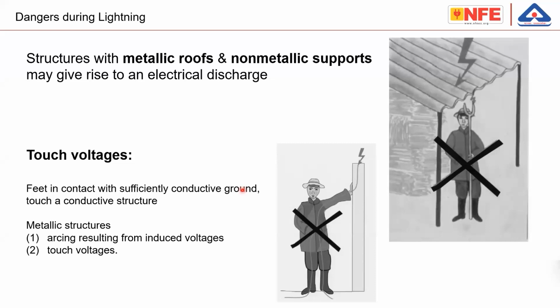Whereas if you are standing outside any kind of building and touching the metallic part, this problem exists. So touch voltage exists outside the building. I repeat: if you are standing inside a building which has steel reinforcement and protective equipotential bonding as per IS 732 or National Electrical Code, then inside the building this problem doesn't exist, but outside the building touch voltage exists.